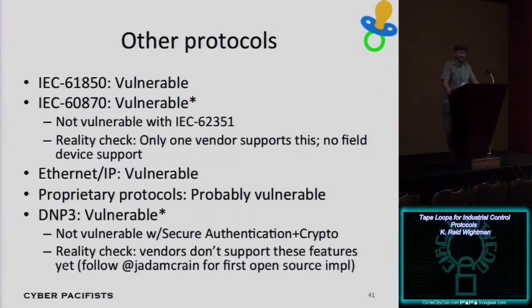DNP3, as implemented in most devices, is vulnerable to this. There's a thing called DNP3 SA, where SA means secure authentication. It's another one of these TLS add-ons to a classic industrial protocol. It adds authentication, and it actually does mutual authentication of the field device and the HMI or OPC system.